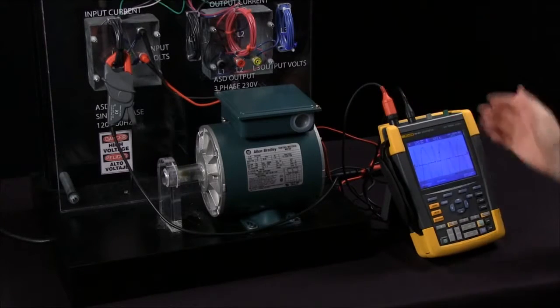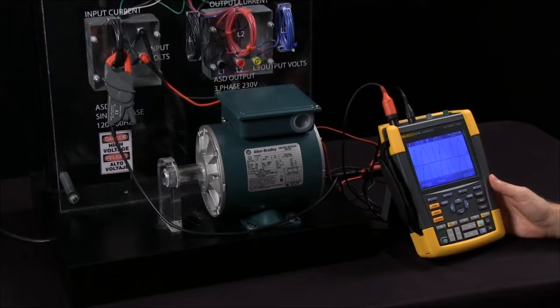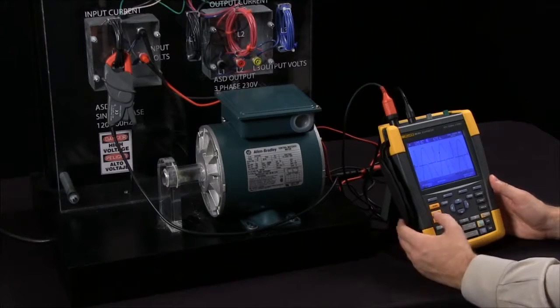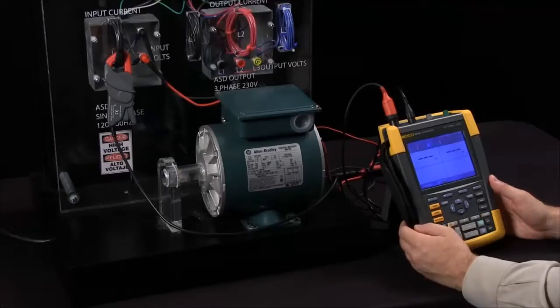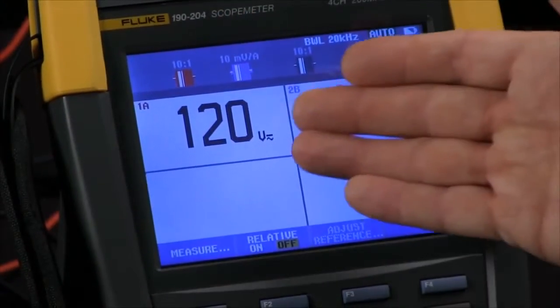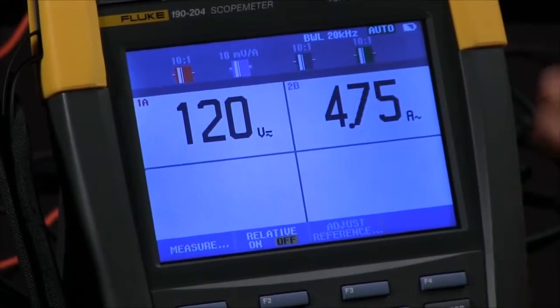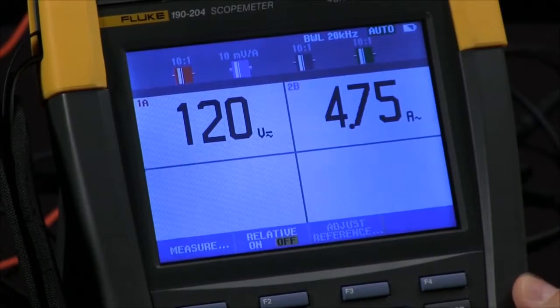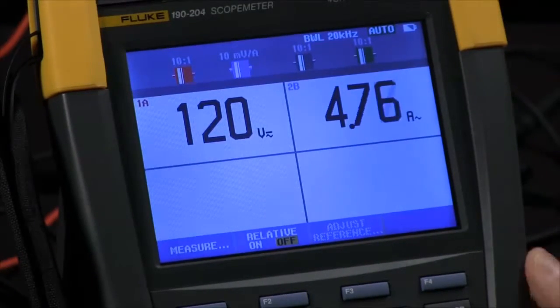In your scope mode we're looking at the input voltage and current to the drive. I can also shift into meter mode and now we're just displaying this as a numerical value. So there are my 120 volts on the input of the drive and I'm also drawing 4.75 amps.